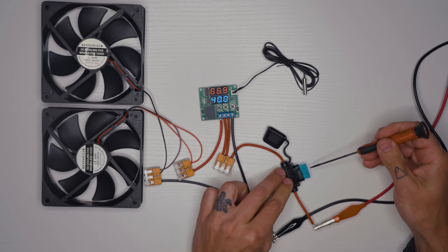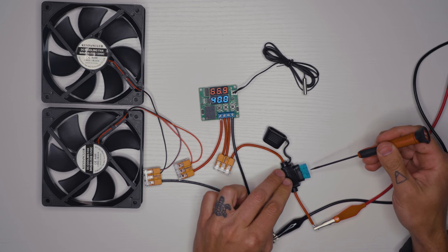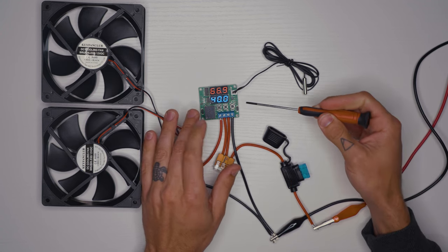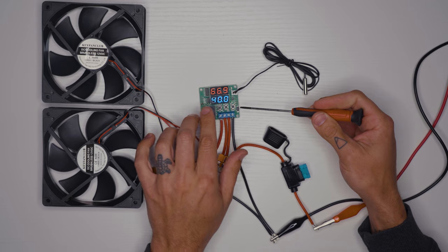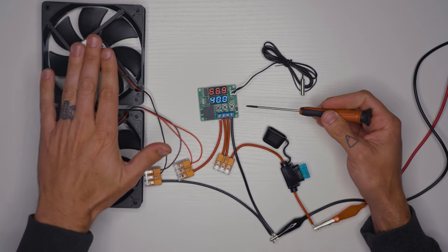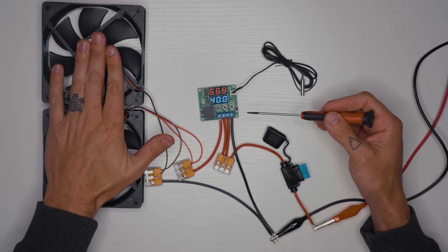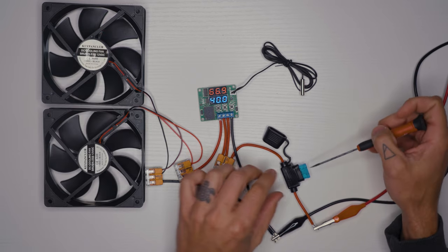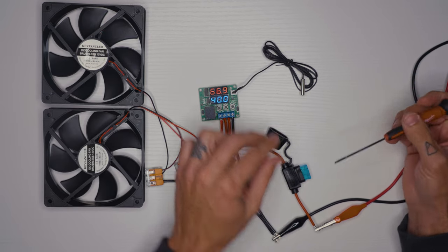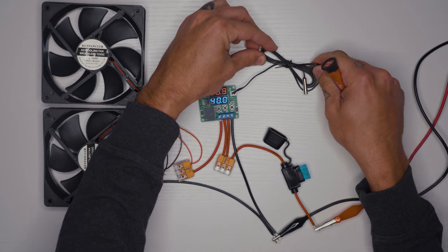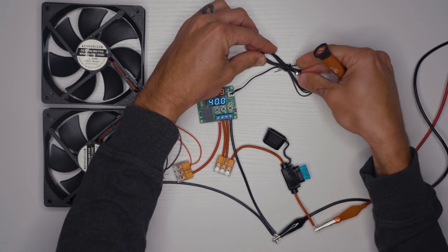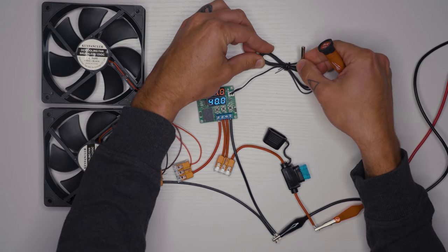It's important to note that there's a fuse here. It's a 3-amp fuse. This particular thermostat is rated up to something like 10 amps, but each of these fans is only pulling like 0.1 amps, so we can use a really small fuse here. And this is the temperature sensor with the little temperature sensor probe on the end.